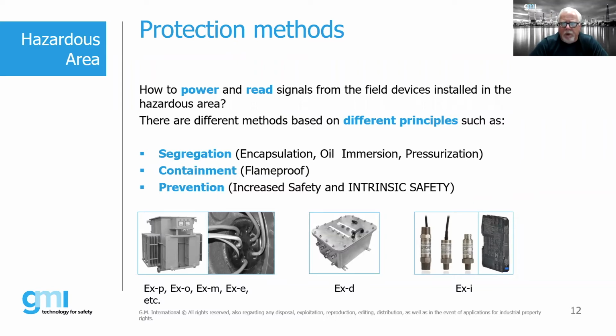Containment is basically flame-proof or explosion-proof, where we basically assume we're going to have all three legs of that triangle, but the design of a flame-proof box is such to where it'll contain that explosion safely, allow that hot flaming gas to escape via the flanges, via the thread paths or the flame paths. And then, of course, prevention is really increased safety and intrinsic safety. So increased safety deals with creepage and clearance requirements for energized components, where we have to maintain certain distances between individual circuits. And we do that to make sure that there's no arcing or sparking by the use of special terminals or other devices. And then, of course, intrinsic safety is also a prevention technique. And here we're talking about basically keeping the amount of energy below the ignition curves of the particular gases and vapors. So these are our three main concepts: segregation, containment, and prevention.